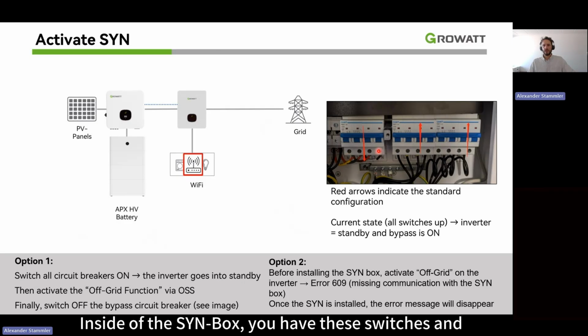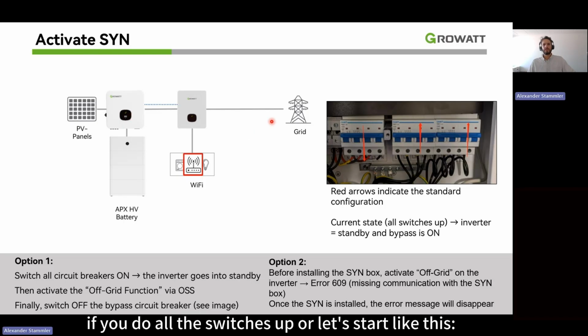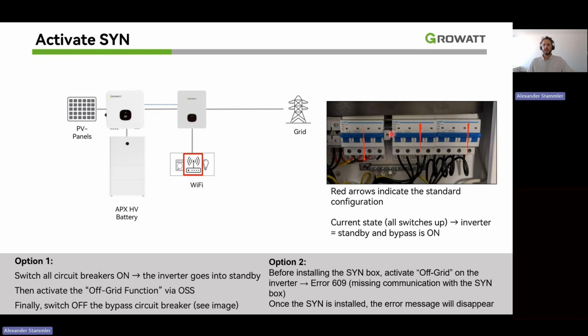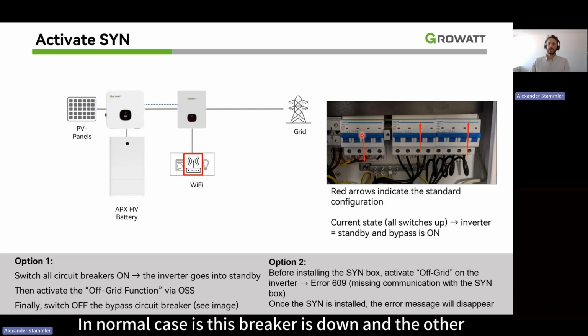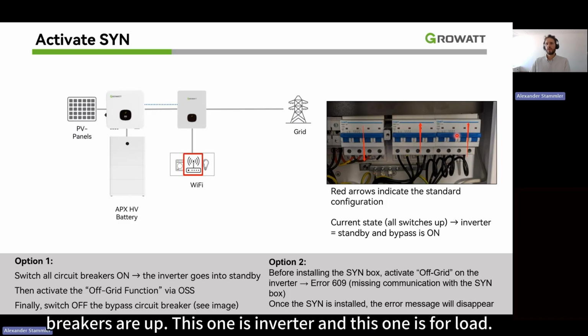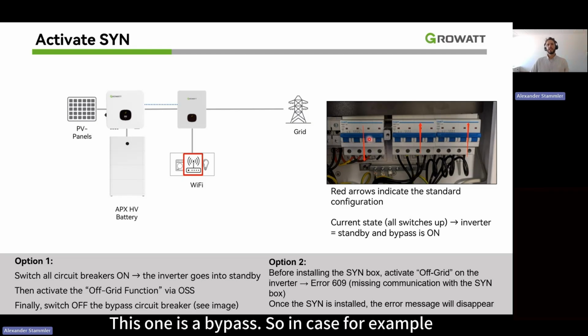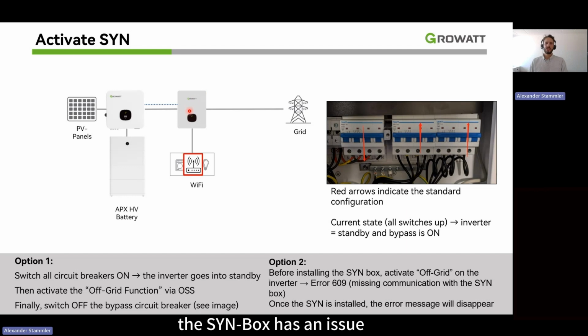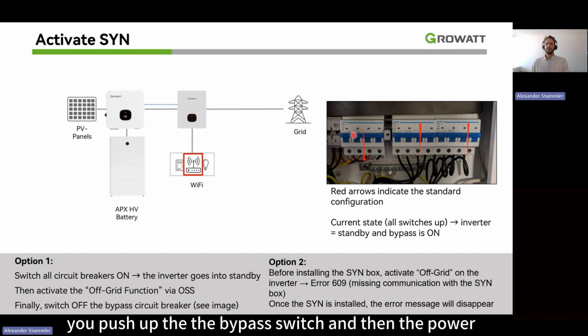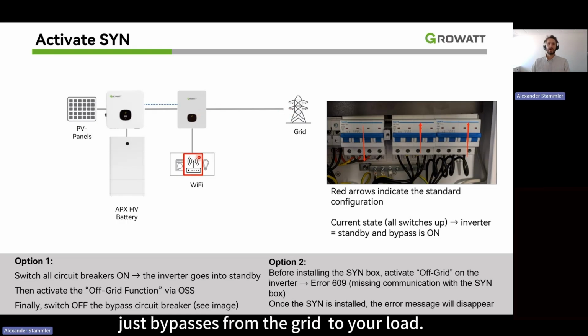Inside of the SYN box, you have these switches. Let's start like this. Normal case is this switch, this breaker is down, and the other breakers are up. This one is inverter, and this one is for load. This one is a bypass. So in case, for example, the SYN box has an issue, you push up the bypass switch, and then the power just bypasses from the grid to your load. If all of them are up, then the inverter goes into standby.